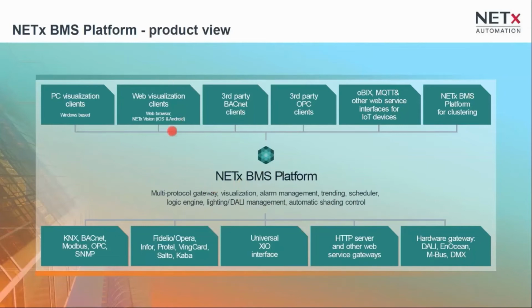Also, we provide our own visualization clients, independent if you want to run on a PC, in a tablet or in a web browser. But also, you may connect any third-party system. For third-party connectivity, we provide interface to BACnet clients as a BACnet SCADA control system, to OPC DA and OPC UA clients as well, or the web service interfaces like OBIX or MQTT. And last but not least, you may connect multiple sites to one system.